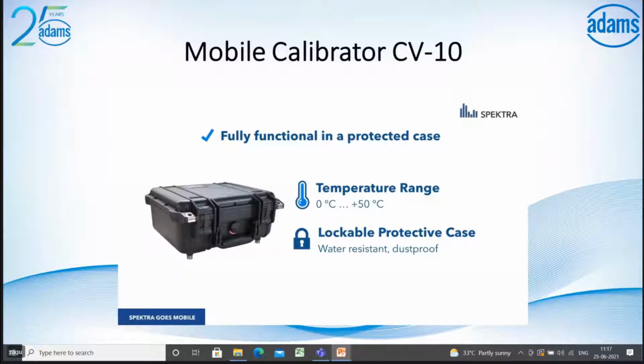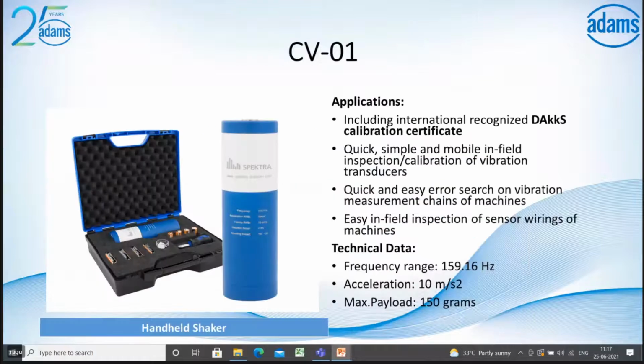So, CV01, it's a handheld calibrator. This is specially designed for on-field verification of your measuring sensors. So before going for the measurement, you can make sure your sensor is working properly by exciting known frequencies, such as 159.16 Hz and 1 g RMS.